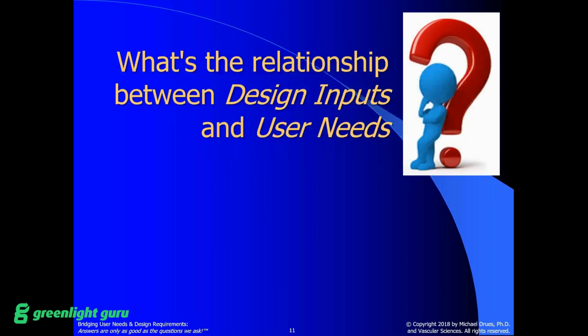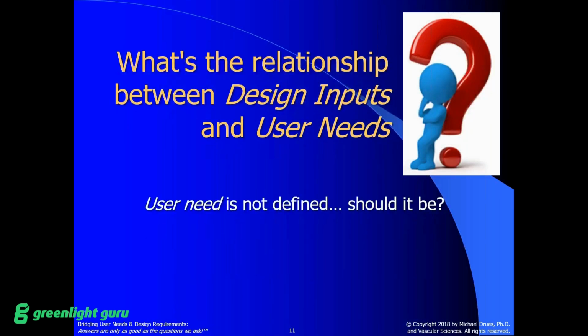You can come up with what you think should be the user needs, but you should verify those with your actual users. This is another example of how it's more important not to understand the wording of the regulation, but the intent of the regulation. So the intent of the regulation, and we'll talk about the limitations of this in a moment, is to make sure that we start out with addressing the needs of the actual user, and then we translate those into engineering terms, what we call design inputs.